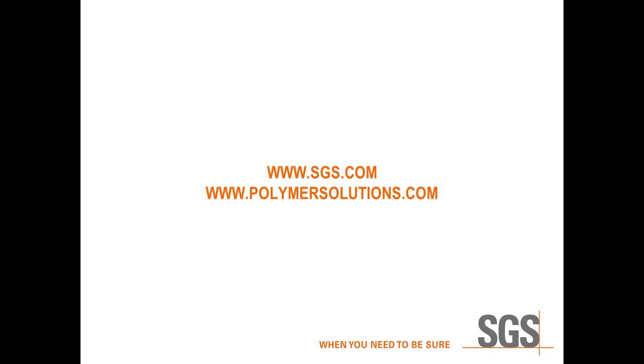Is there an advantage to using MALS versus dual angle light scattering for polymers smaller than 100K? Yeah, I don't know if there's really an advantage in one technique versus the other. The thing I like about MALS versus dual angle light scattering: most dual angle light scattering instruments are calibrated by injecting a polymer standard of known molecular weight, and then you use that standard to establish a calibration constant for your dual angle light scattering detector, whereas with a multi-angle light scattering detector, the way that those are usually calibrated is by infusing toluene into the flow cell.